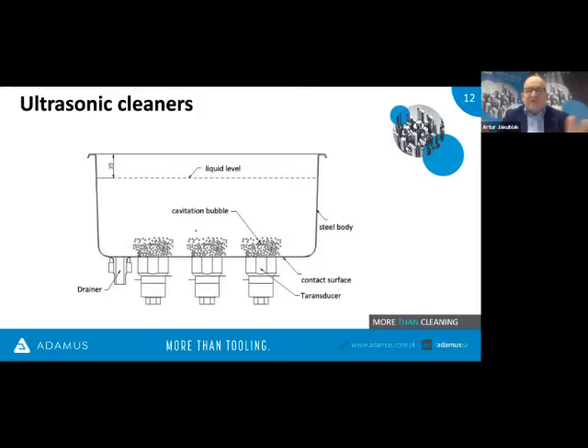This is a very general view of the ultrasonic cleaner. You see here the cavitation bubbles, which we talked about a while ago with this cavitation mechanism. This is a steel body, of course. This is a tank with the liquid level. We have transducers which transfer the electrical energy to this ultrasonic energy. We have a contact surface, and we have a drainer, of course, if we would like to drain the liquid after the cleaning, just to clean the machine.